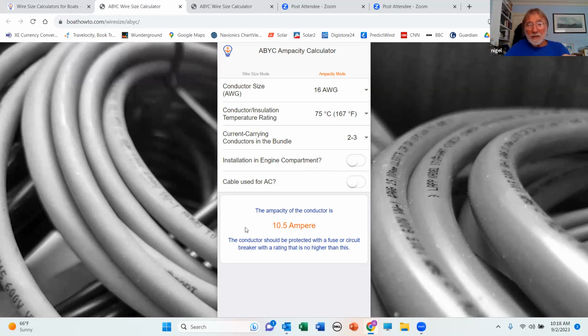This ampacity is unrelated to length. Voltage drop is absolutely tied to length because the longer it is, the more the cumulative resistance. But ampacity is not, because as the conductor increases in length, the surface area increases proportionately, so you've got more heat dissipation capability. So it doesn't make any difference how long the conductor is. It's the number of amps you're putting through it that's going to determine whether it melts down or not, however long it is. So in this case, we've got a 10.5 amp limit for this 16 gauge conductor that you found in your boat with a 75-degree temperature rating.